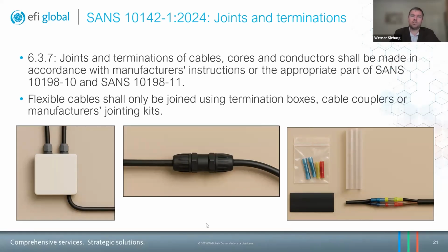So 6.3.7 is joints and terminations. A core and conductor shall be made in accordance with manufacturer's instructions. So once again, if there are manufacturer's instructions as regards how to make a joint, that needs to be taken into account. And then there's an OR. It needs to be the appropriate part of SANS 10198, parts 10 and 11. So that deals specifically with cable joints, also more in the context of large caliber, large gauge cables, but also applicable to smaller cables.